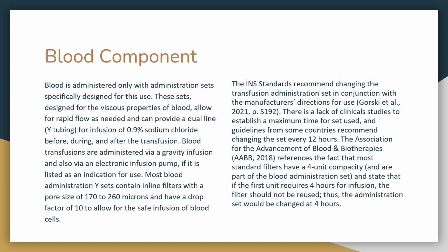You do need to understand that their bore is so large that they have a large drip factor to allow for this. Now, the INS, which stands for Infusion Nurses Society, recommends changing those administration sets per the manufacturer's recommendations. However, it's usually every 12 hours.